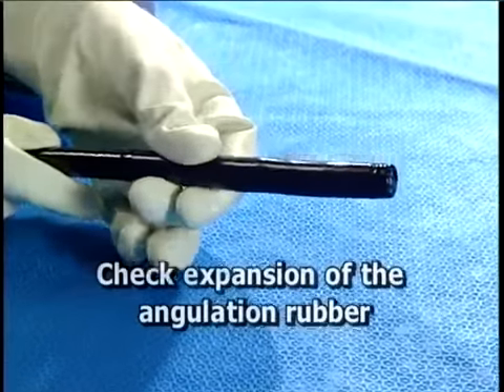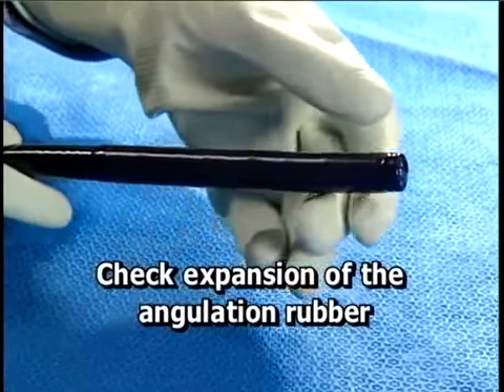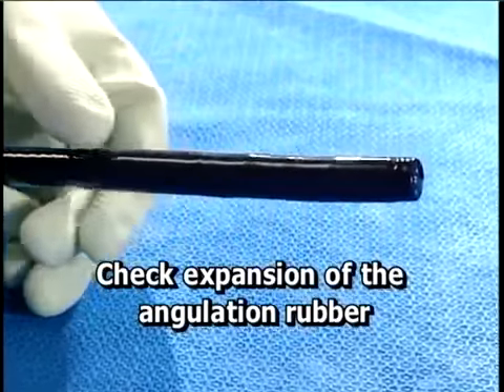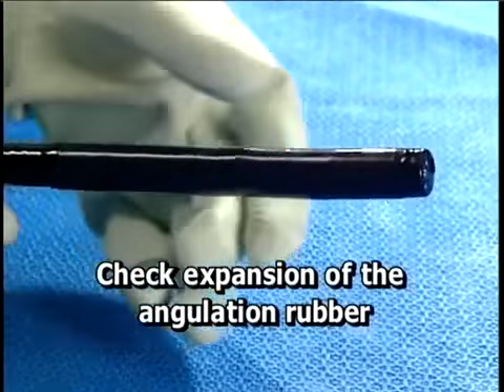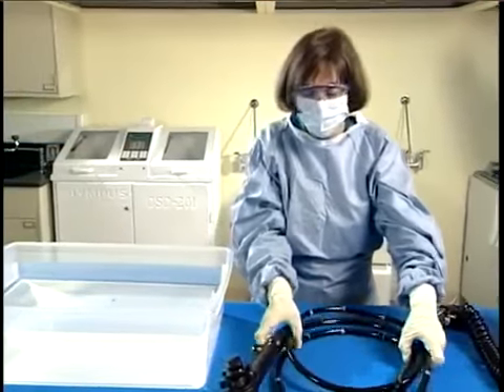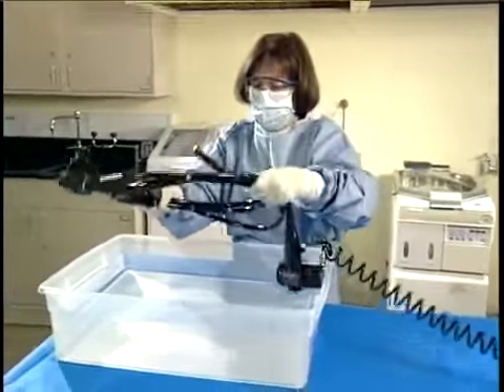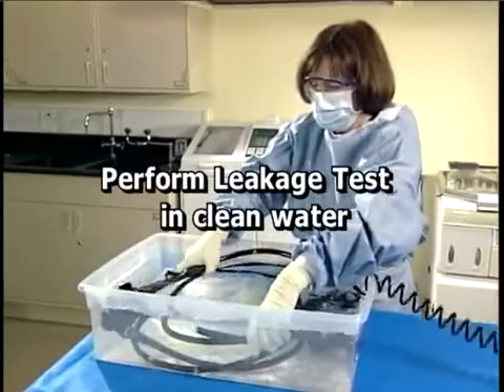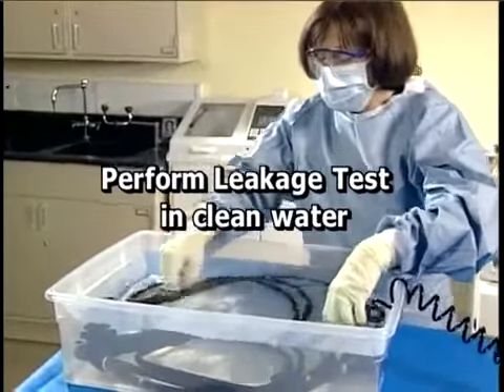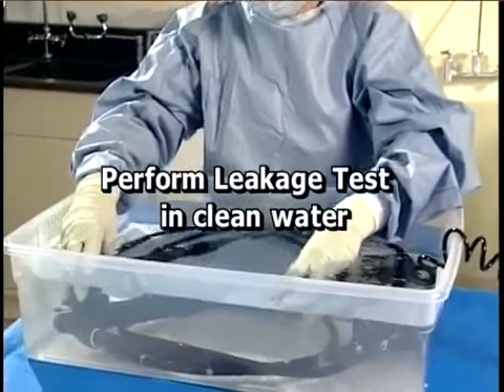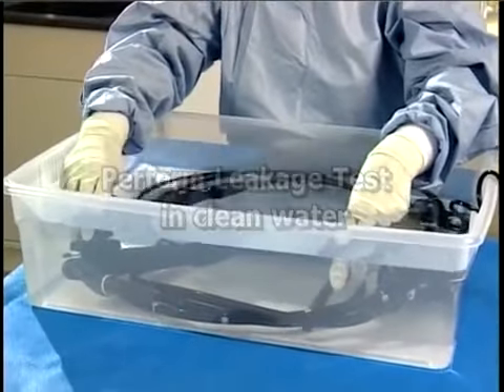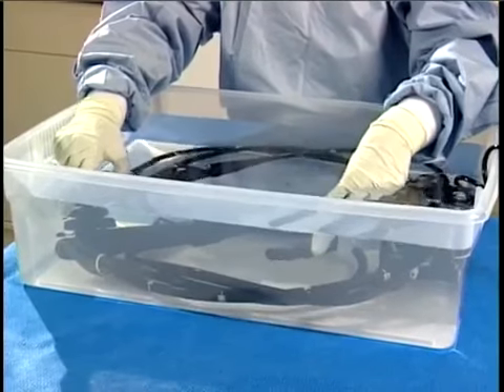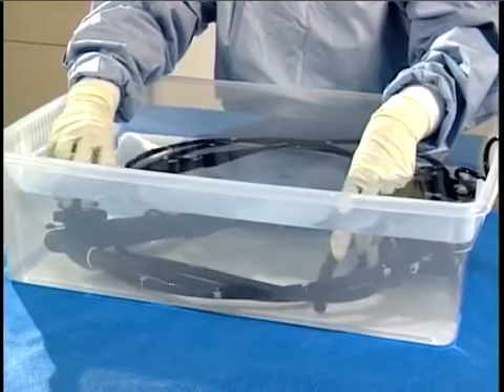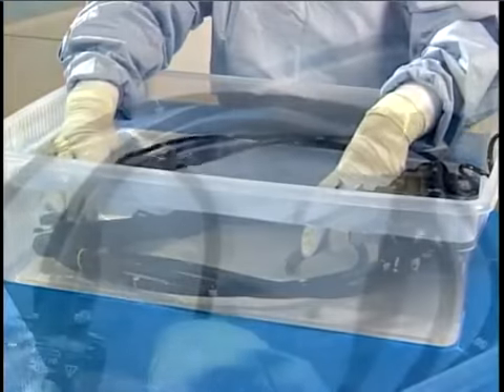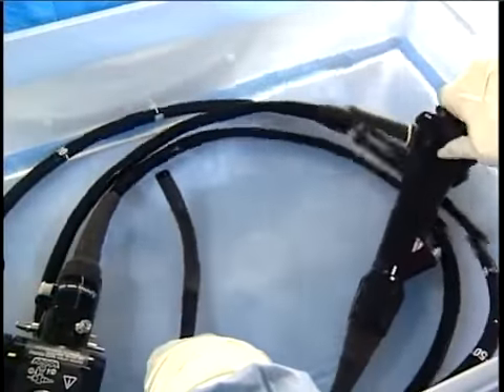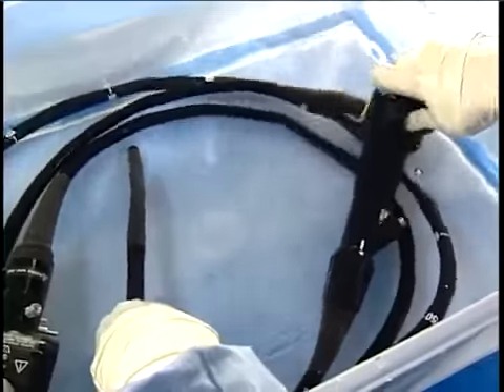Note that as you pressurize the inside of the endoscope, the rubber sheath on the distal tip of the endoscope will expand. Now, immerse the endoscope in clean water. Do not leak test in detergent, as detergent will hinder visualization of leaks. With the angulation locks in the free position, angulate the endoscope tip in all directions. Deflecting the tip will help expose any pinholes that may exist in the bending section rubber.